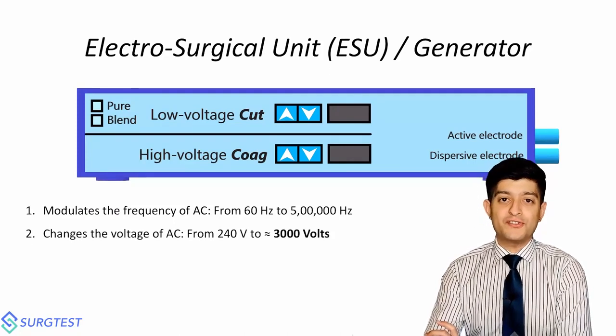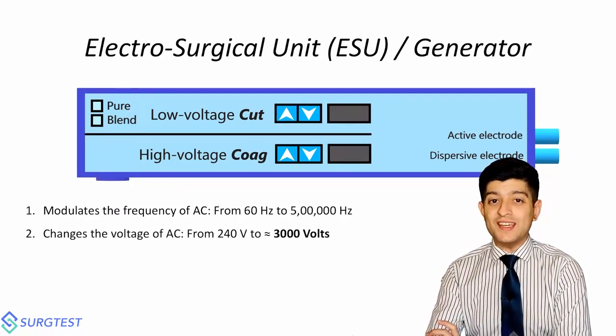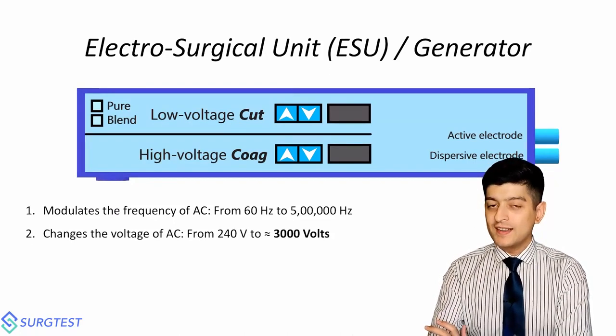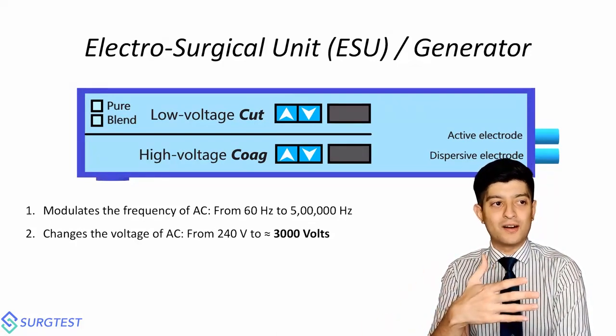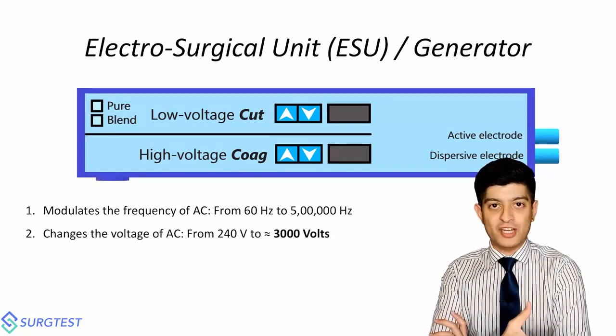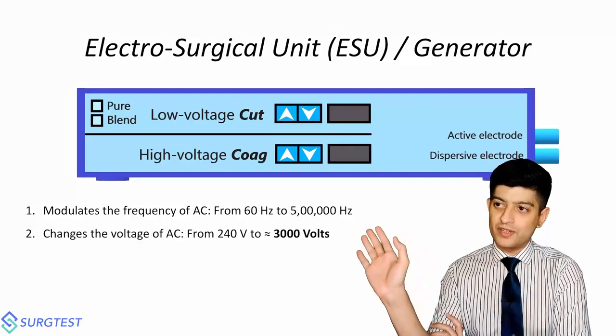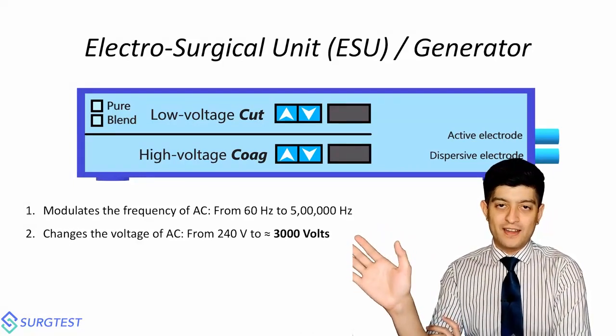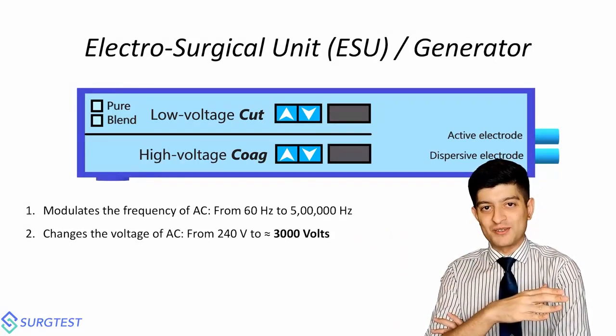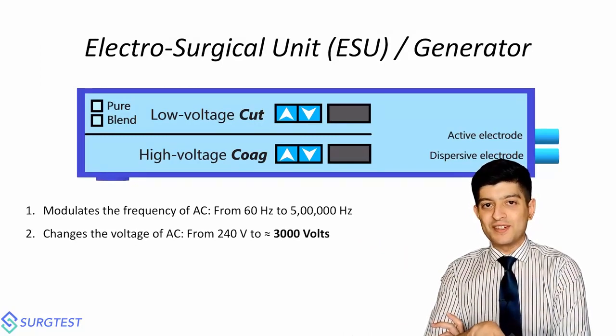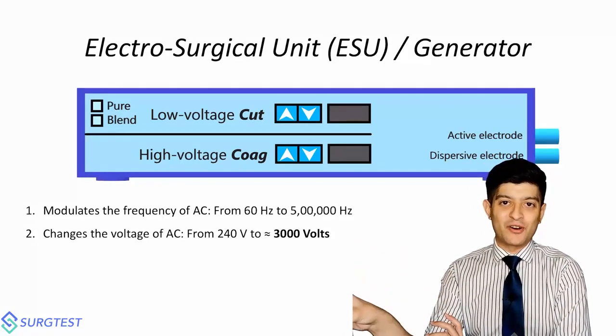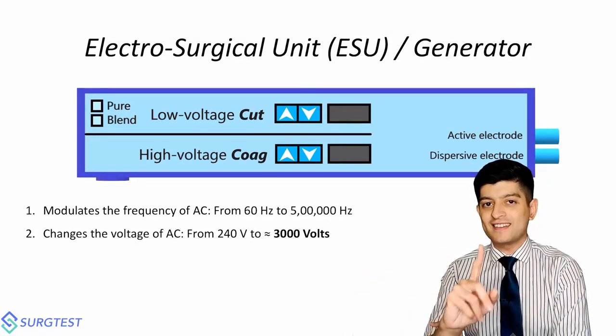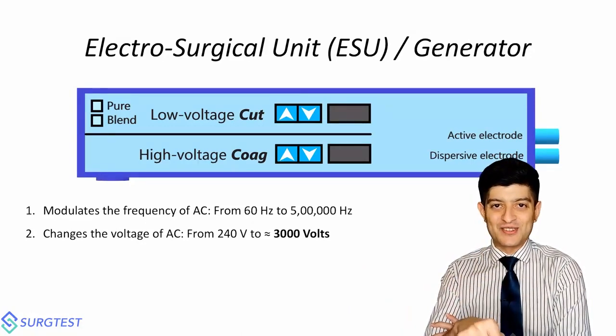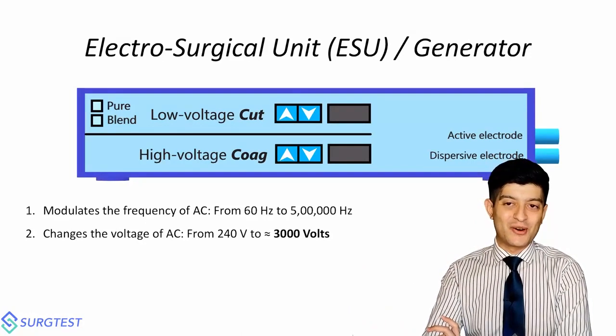Additionally, it changes the voltage from 240 volts to close to 3000 volts. Think about it. When you go down to your building mainframe and check out the voltage that has been printed, it's usually around 400-ish, and there is a big skull and crossbones present over there. Imagine if you had that sort of a danger warning attached on top of every cautery machine. Actually, you know what? That is a great idea. At least that way surgeons will start paying more attention to their cautery devices.